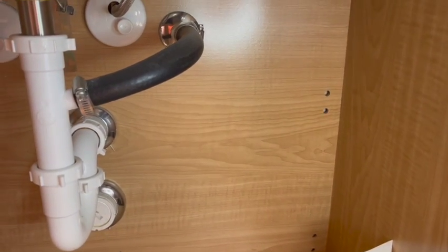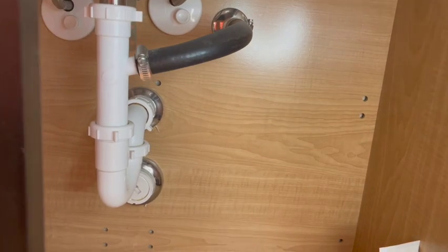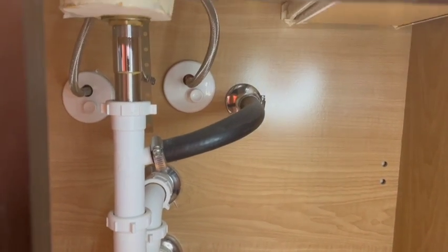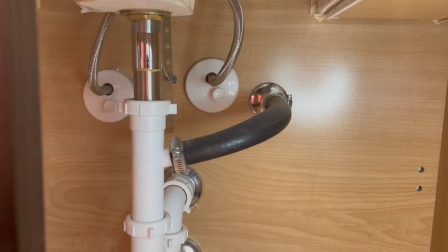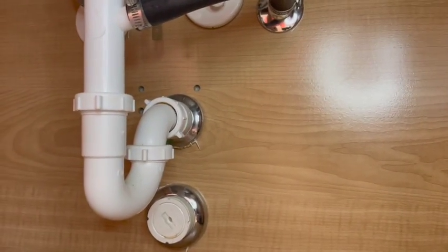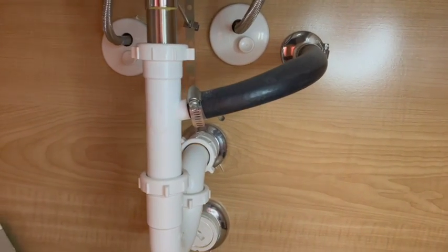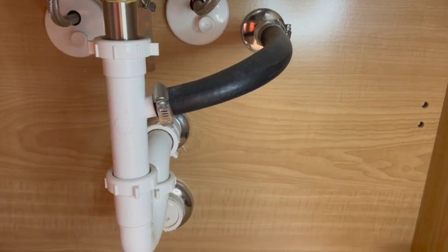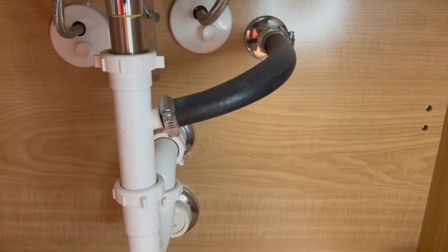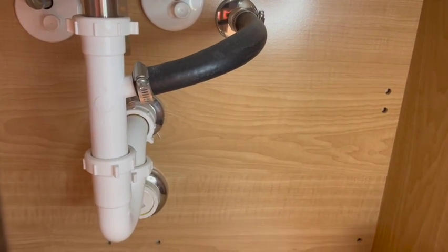Okay, we are here in the master bedroom or master bathroom to take a look underneath the vanity to see what we can find for a condensation line. If you look underneath here, there's a black rubber hose coming out of the wall. That is going to be the condensation line that goes into the drain here. This is the primary condensation line, so we know it does not go to the exterior. It does go into the main drain, so that is good.